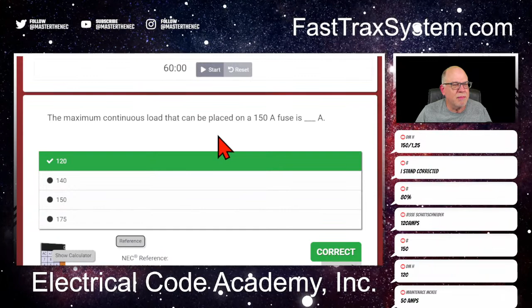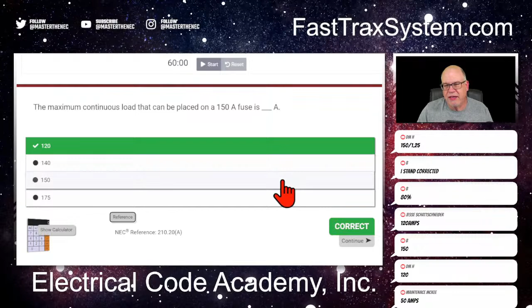All right, so there's your answer, 120. And again, you just simply take the 150. Now I'm going to take the 150, multiply that by 0.80. It's the easiest way to do it. And that's going to give you 120. Now, if I were to be given 120 amps on a question and it says take that as a continuous load, then I would take the 120 times 1.25. And that's how we get the 150, right? So see how they're reciprocal? Just keep that in mind. You're not going to see anywhere in the code refer to 80%. So you have to understand that 80% is the reciprocal of 125%. And that's going to do you a lot of benefit as you move forward in understanding those nuances.